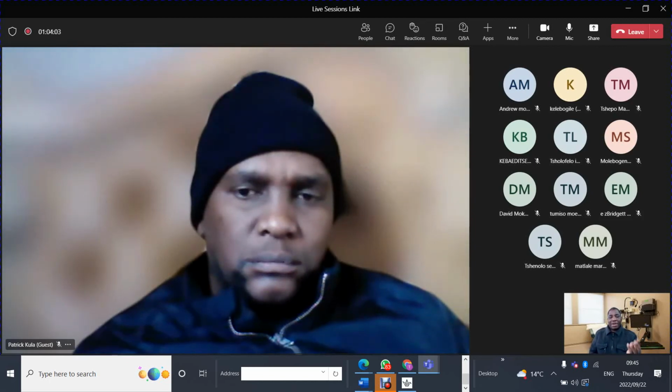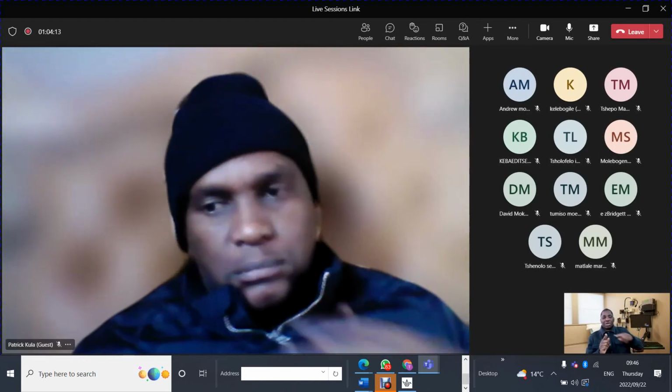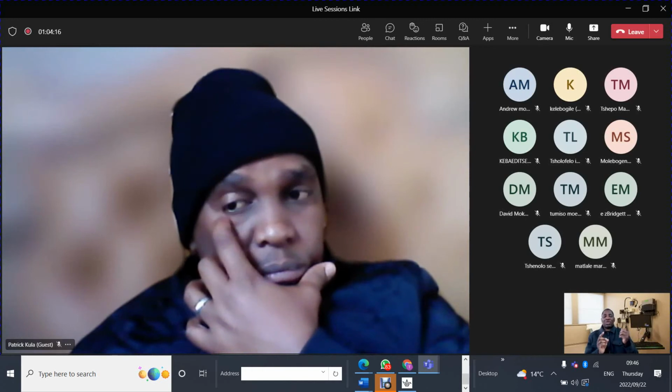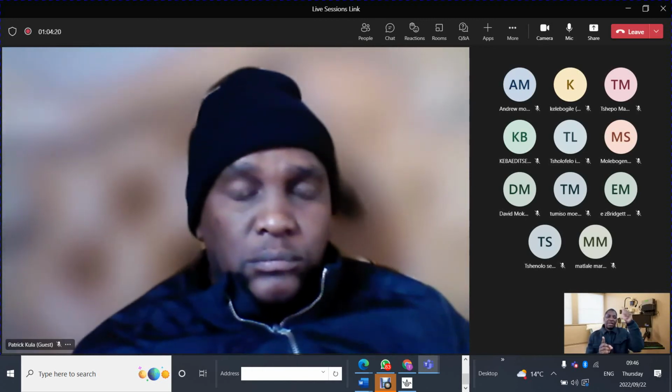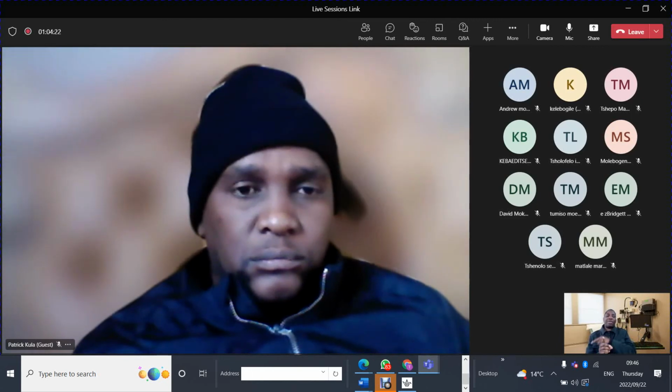And that can create a hazard that will lead to electric shock. We don't want that. So we want the current to flow through that closed circuit. It must not go to ground, because to go to ground, it has to pass through a path other than the path created for it to follow through the active patient dispersive electrode back to the machine.